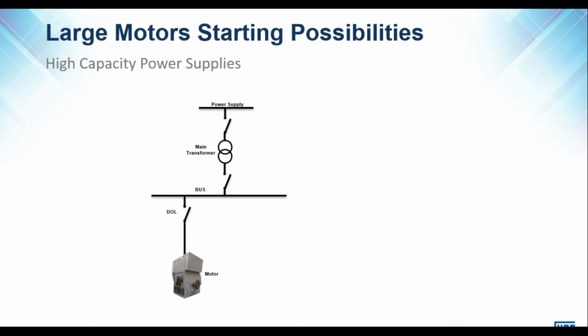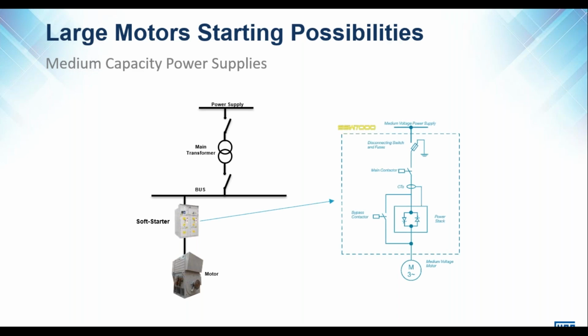All right. If a power plant or an industrial plant can handle a high capacity, high impact starting current, in other words, if there is a high capacity power supply, direct online is arguably your best option, depending on other considerations, of course, like mechanical stress and strain on the equipment. For medium capacity power supplies, a soft starter or low inrush current design motor is a good option. This just shows the topology of a typical medium voltage large soft starter.